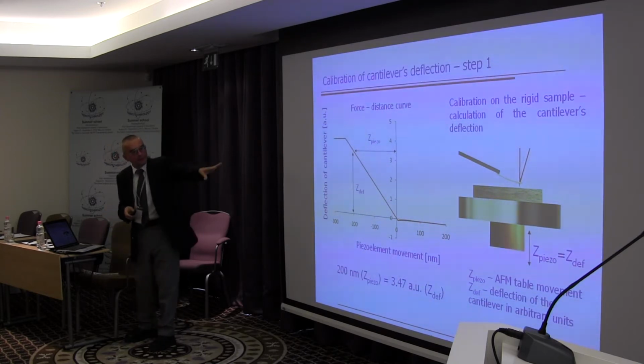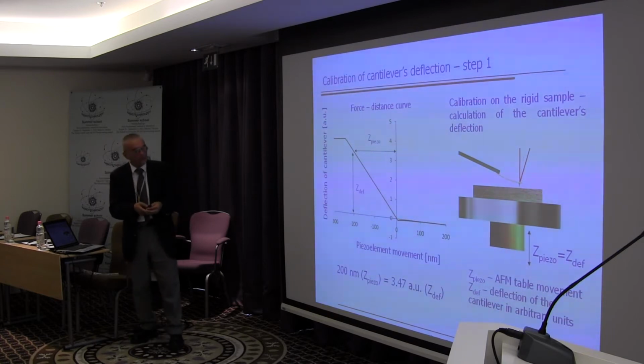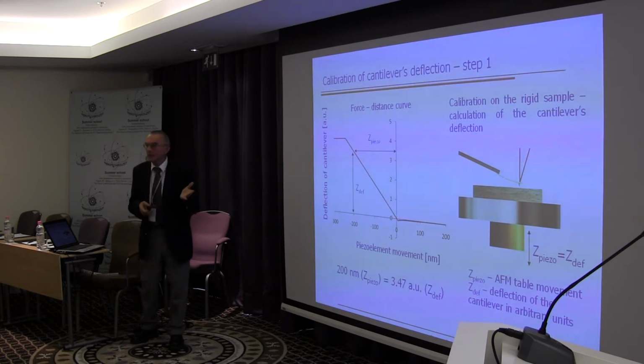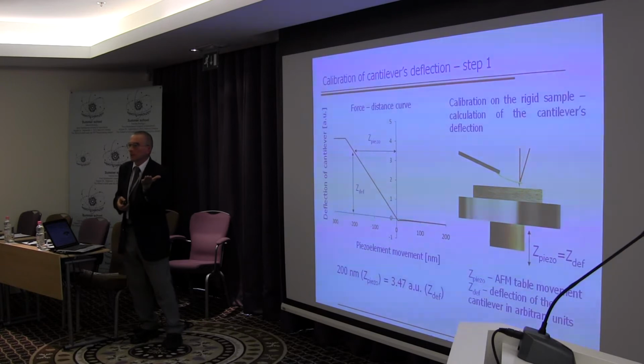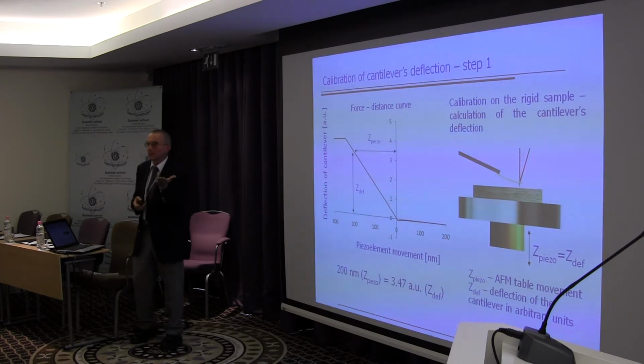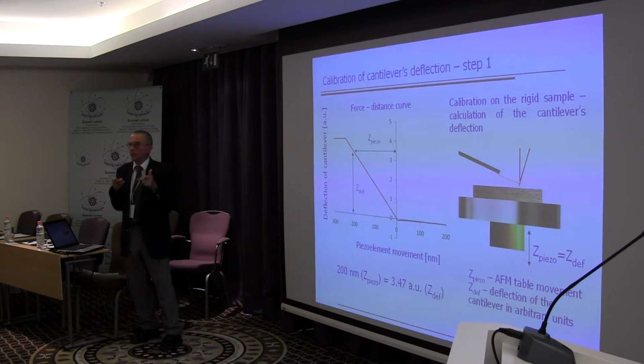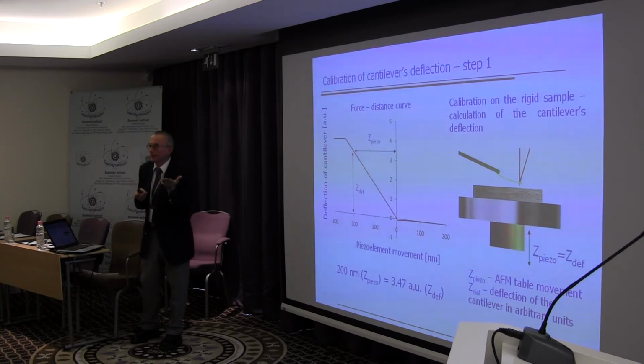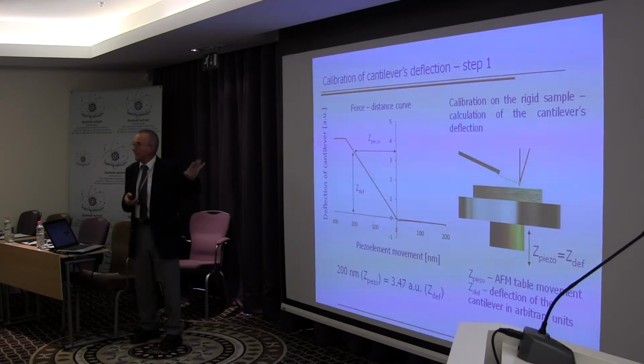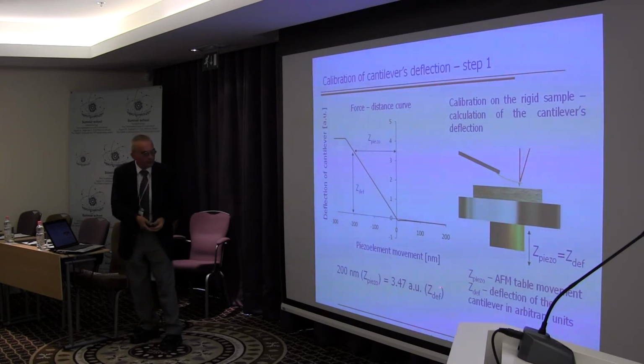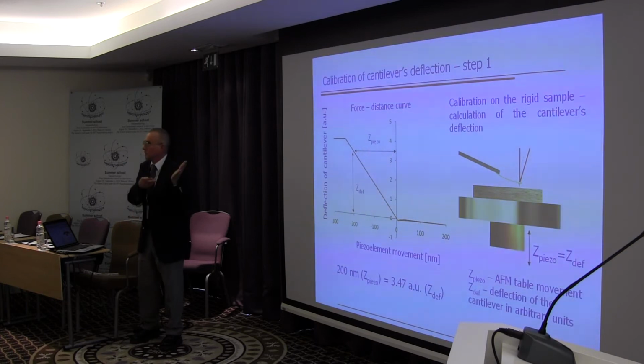So firstly, we are doing an experiment using our atomic force microscope on the cantilever. We are doing something like a force distance curve using a very stiff material, like thin crystal silicon. It is okay for us. So we assume that there is no deformation in the contact area between the tip and our silicon sample. In this way, we can identify the stiffness of the cantilever, but unfortunately we have arbitrary units. But we know the stiffness.